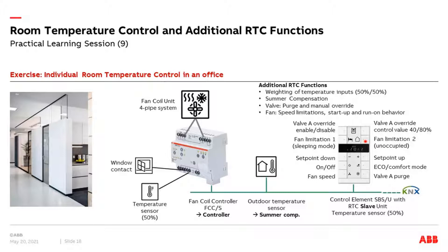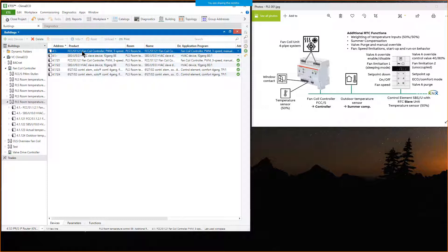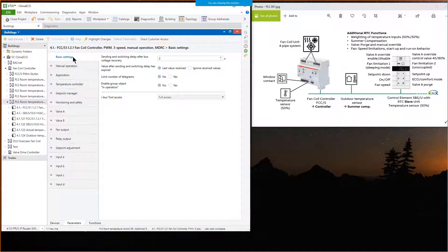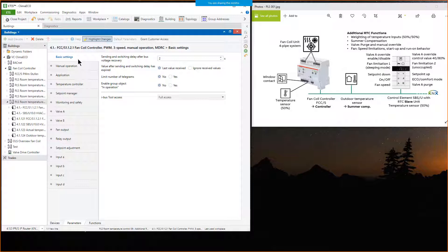Let's do exactly the exercise and I show you now the parameterization in the ETS. I have prepared the ETS project with the fan coil controller FCCS with the three-speed motor and thermoelectric valve outputs. I start with setting the parameters of the fan coil controller. I activate the 'highlight changes' function — so when I change a parameter, it becomes highlighted in yellow, making it easier to follow my steps.